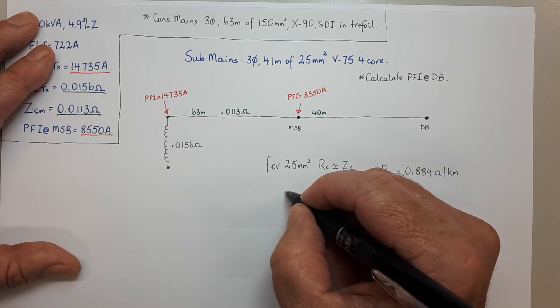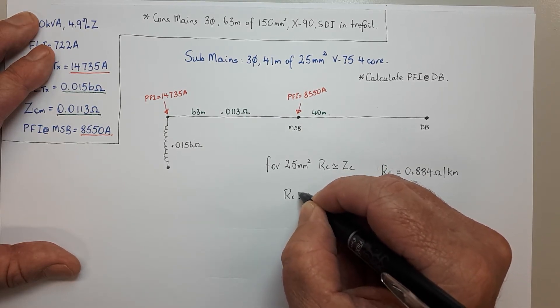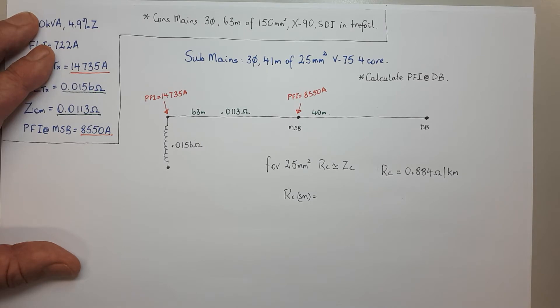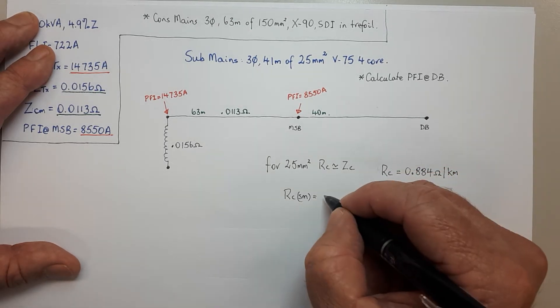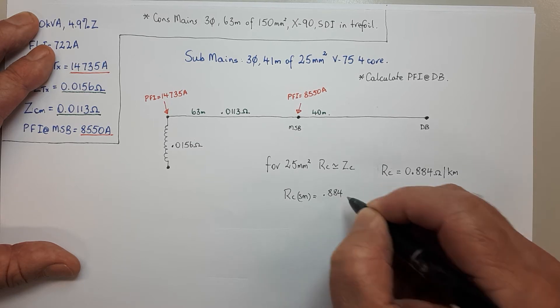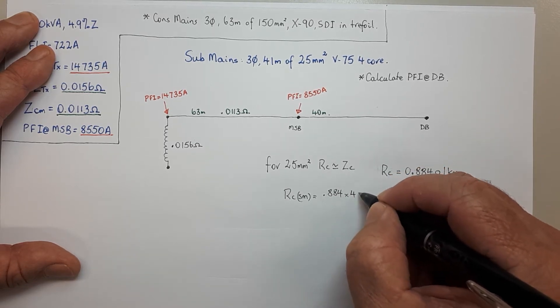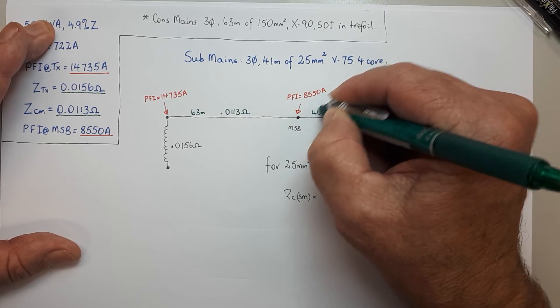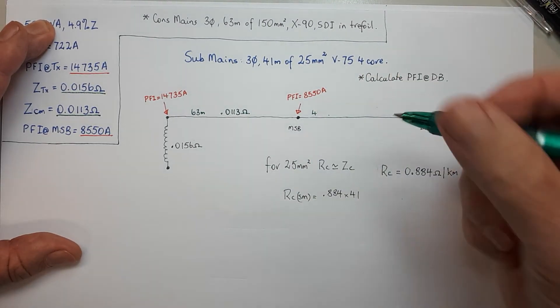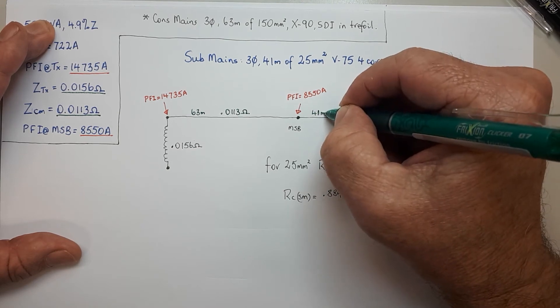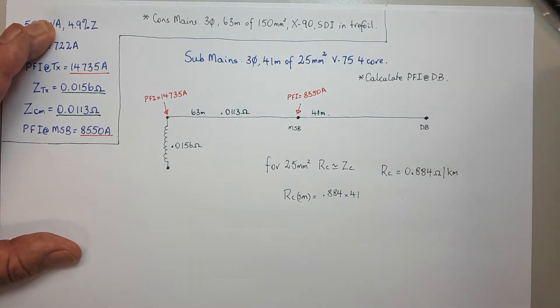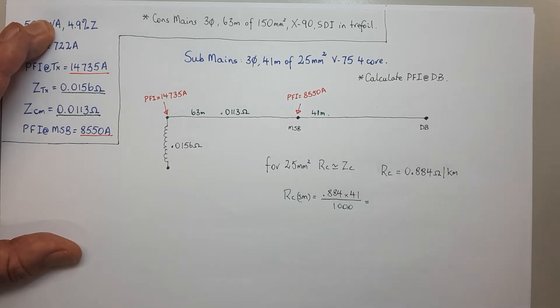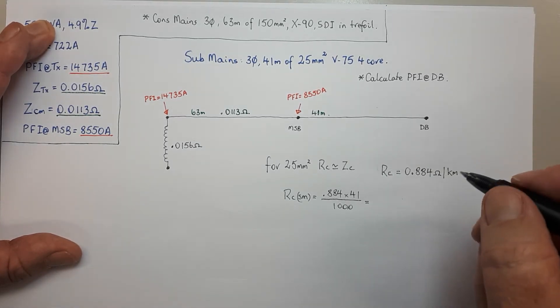Therefore we can work out the RC for the sub-main: 0.884 ohms per kilometre. Hopefully you picked up the mistake I made — deliberate TAFE teacher mistake. I put in 40 metres there but it's actually 41. I advise you to get one of these rub-out pens, they're awesome. So that's 41 metres, in line with what it is there. Over 1,000 of course, and from banging that into the calculator we get 0.0362.